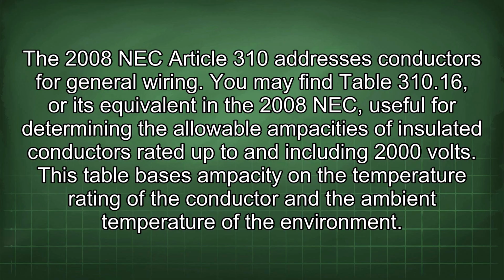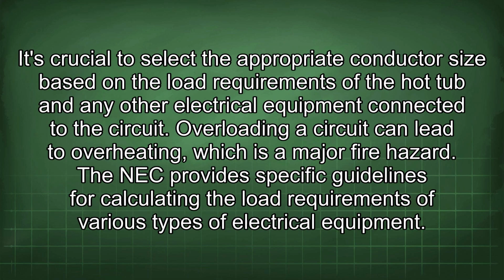This table bases ampacity on the temperature rating of the conductor and the ambient temperature of the environment. It's crucial to select the appropriate conductor size based on the load requirements of the hot tub and any other electrical equipment connected to the circuit. Overloading a circuit can lead to overheating, which is a major fire hazard. The NEC provides specific guidelines for calculating the load requirements of various types of electrical equipment.